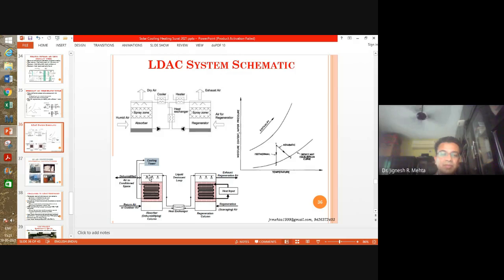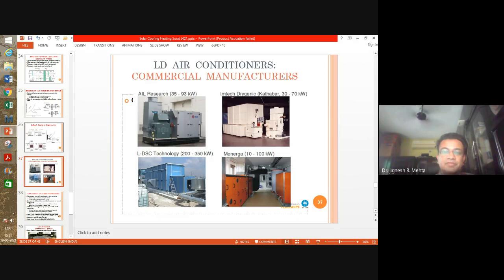Okay, so this cooling may be provided with an ambient tower, cooling tower, and then here your liquid desiccant has absorbed moisture from this air, so it becomes dilute. Right, there is water in that which needs to be removed if you want to continue or recirculate it. So that is done in this regenerator where you need to supply heat. This heat can come from a solar thermal collector. So desiccant systems can also be used for solar thermal. So solar thermal collectors can be used for desiccant-based dehumidification systems.